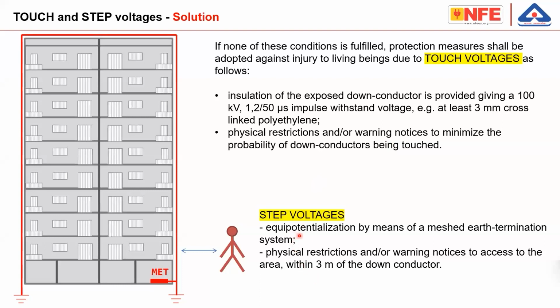Regarding step voltage, equipotentialization by means of a meshed earth termination system will help. Physical restriction: either you make an equipotential meshed earth termination system, I have a picture I will show you next, or you restrict people from going near the down conductor. They have to keep 3 meters away from the down conductor or from the earthing. So basically, even in a well-protected building, you must keep at least 3 meters away from the down conductor, away from the earth termination system, in order to be safe.